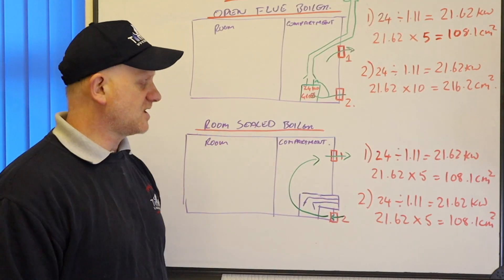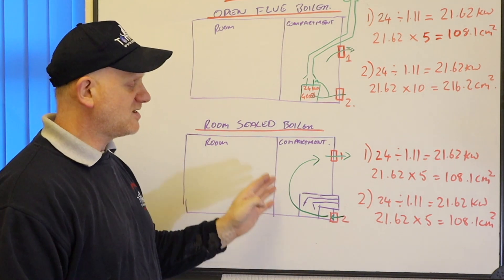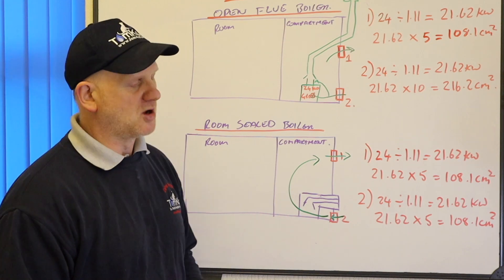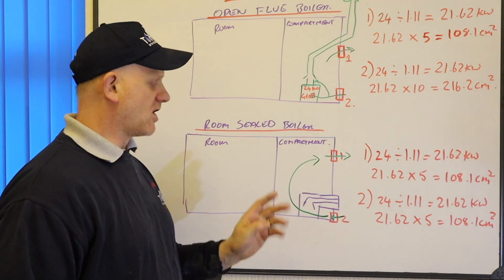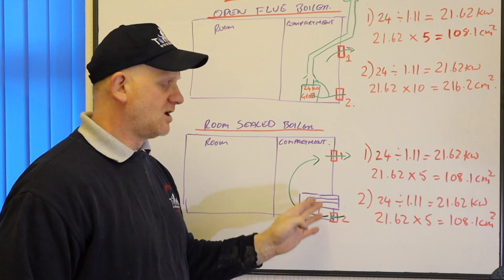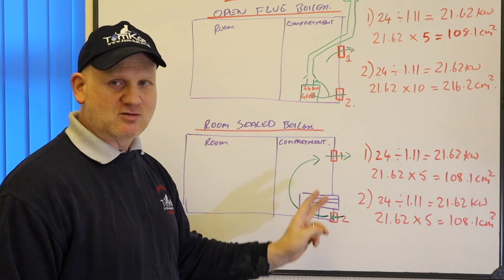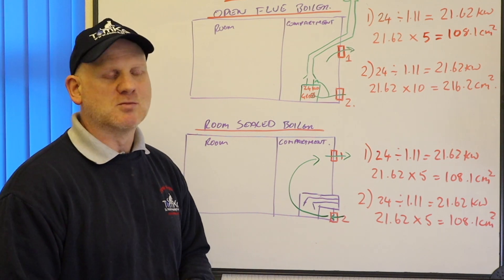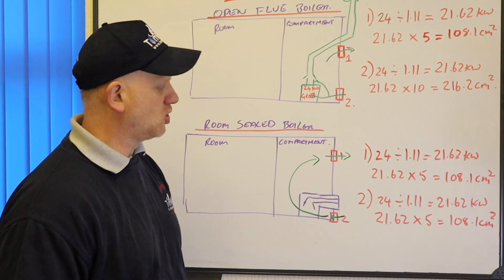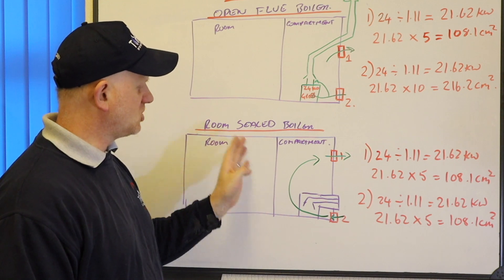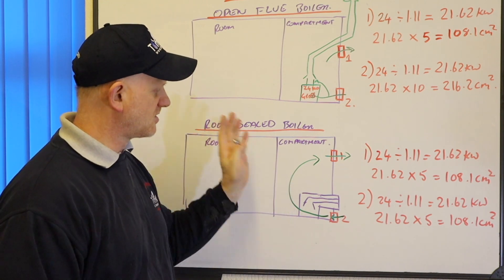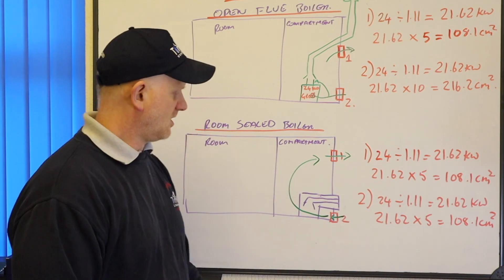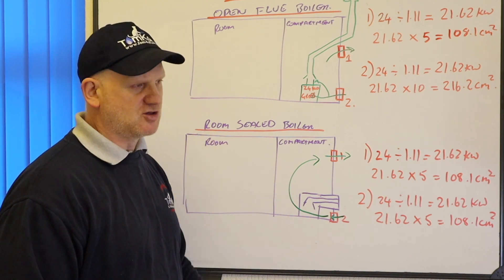So in this scenario here, we've got a room sealed boiler. It's a high water content boiler. That means it's got a cast iron heat exchanger. If they're low water content boilers, they don't normally need vents for cooling. But we've got a floor standing old cast iron heat exchanger boiler here. So it requires two vents coming direct from outside. So we've got 24 divided by 1.11 because it's a 24 kilowatt gross boiler, which is 21.62. 21.62 times 5 is 108.1. And they are the same for top and bottom because we don't need air for combustion. We just need air to cool the room and to cool the appliance. So that's compartment ventilation for room sealed appliances, high water content boilers, which require vents for cooling. Always check the manufacturer's instructions. We would also need a label on the door in this situation which says don't block the vents.